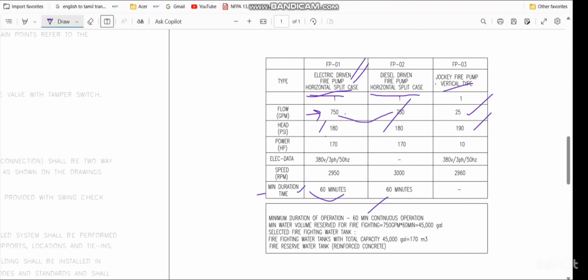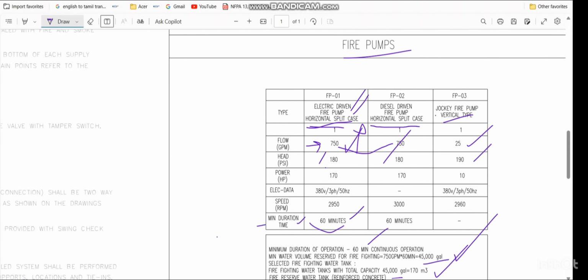So the pump capacity is 750 GPM. So 750 multiplied by 60 minutes will give the answer of tank capacity 45,000 gallon. If you convert the 45,000 gallon to meter cube, it will be 170 meter cube. So the firefighting tank has the capacity of 170 meter cube for the project.